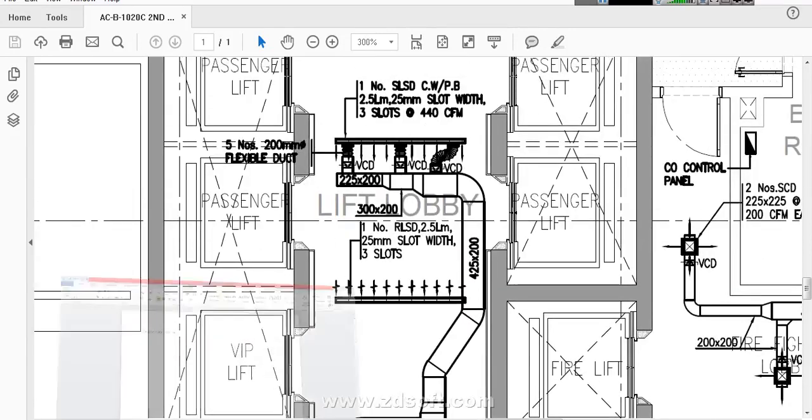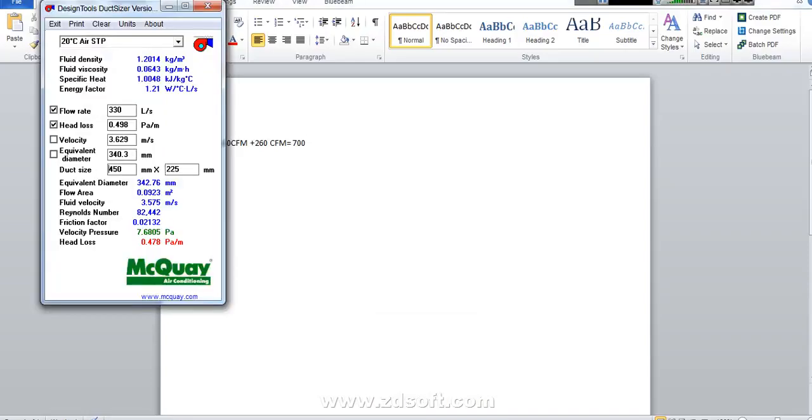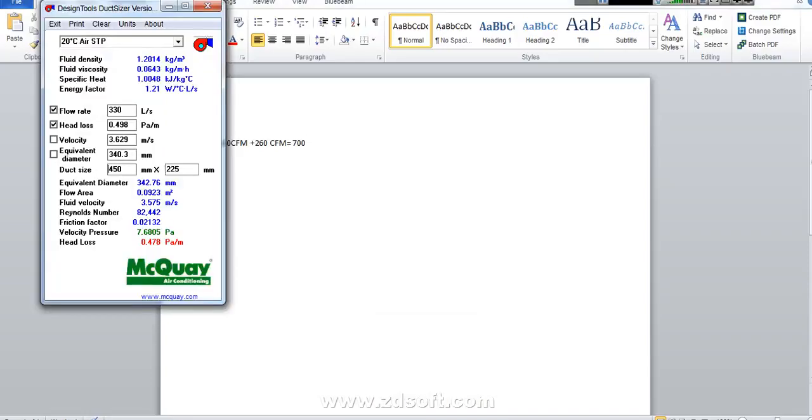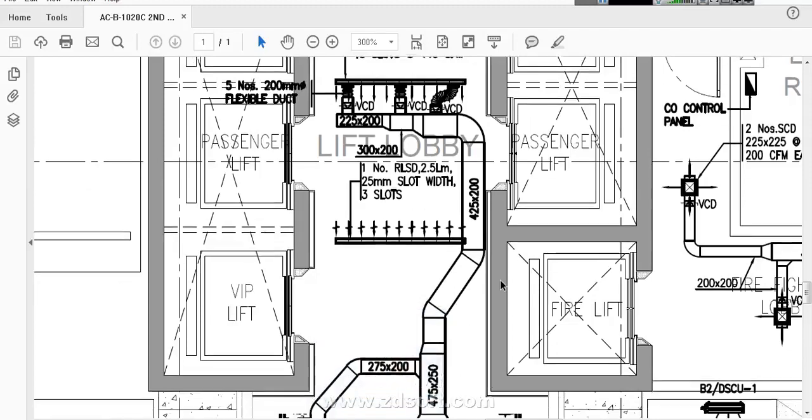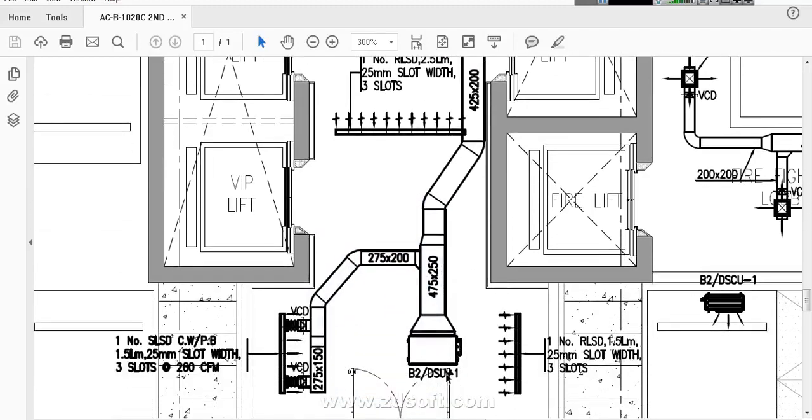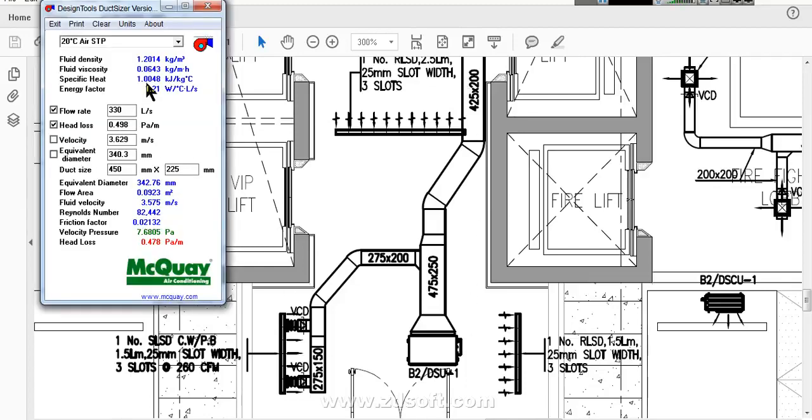The total is 440 plus 260 equals 700 CFM. This 700 CFM we need to enter in our drawing first, because the 700 CFM will start from this machine. So this duct will take 700 CFM air. There is a branch and one straight duct going over here.